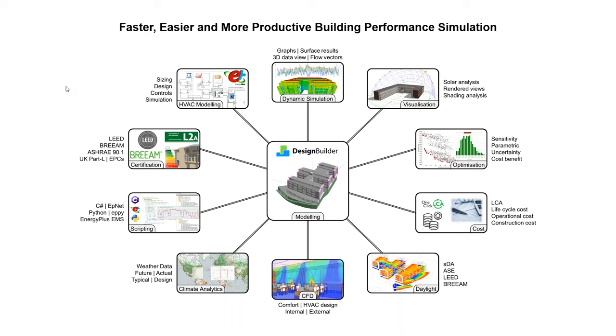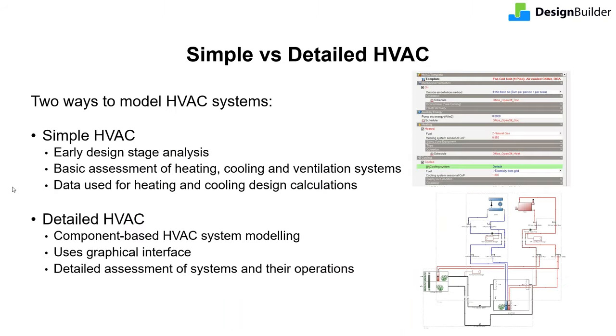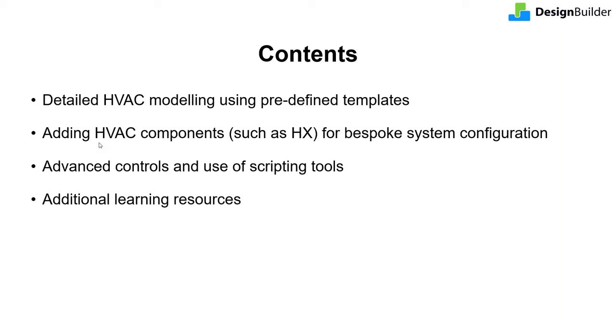Thanks Dave. As a reminder, there are two ways to model HVAC systems in Design Builder: simple and detailed HVAC. Simple HVAC uses EnergyPlus ideal loads mechanism and is suitable for early design stages, whereas detailed HVAC is based on EnergyPlus full systems modeling and uses a graphical interface to model HVAC systems component by component. Today we will focus on advanced aspects of detailed HVAC modeling, including predefined templates, heat exchangers, and scripting tools.